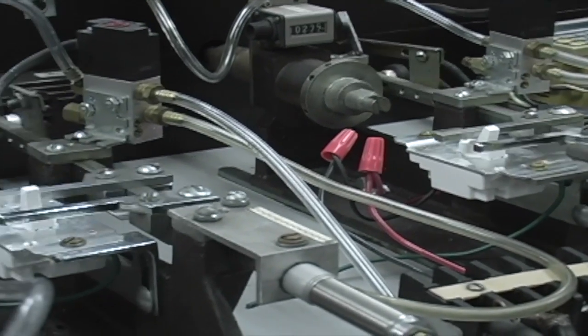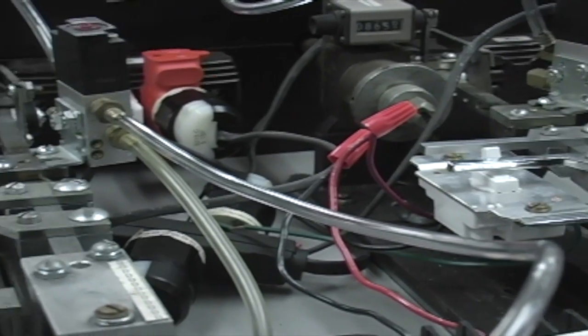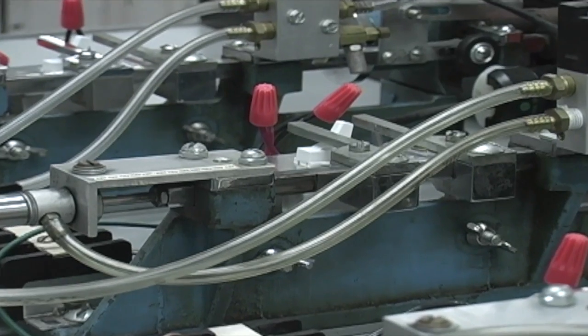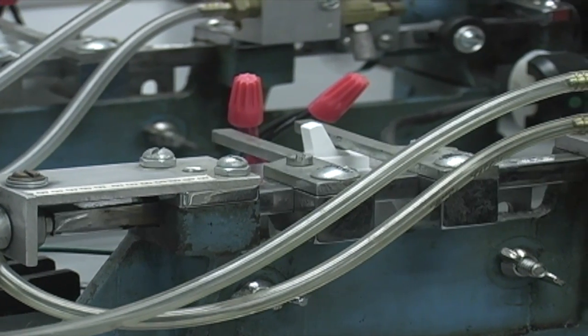What our testing does is simulate a long duration — many years worth of use — in a short period of time. When you're doing torture-type testing and turning things on and off, these are the type of load banks that we use for performing those tests. Different products have different requirements. A typical switch that you'll see in your house will undergo over 30,000 cycles of operation on these types of loads.